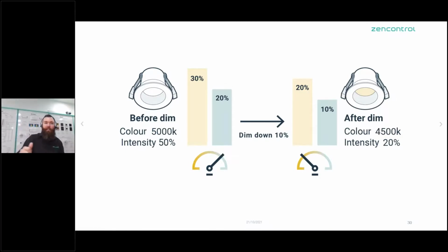And if you dim all the way down until such point that you reach the bottom or the top, one of the devices is going to hit their minimum level, and the color will move back to the same, and it's just going to be 50% between the 2 of them. It's pretty hard, right? On a DALI 2 system, the individual device calculates that for you. So you send dim down 10%, and it actually works out that in this case, it would go to 27 and 18%, which would mean that the color stays the same, I've made a typo there, and the intensity moves down by that 10%, okay?